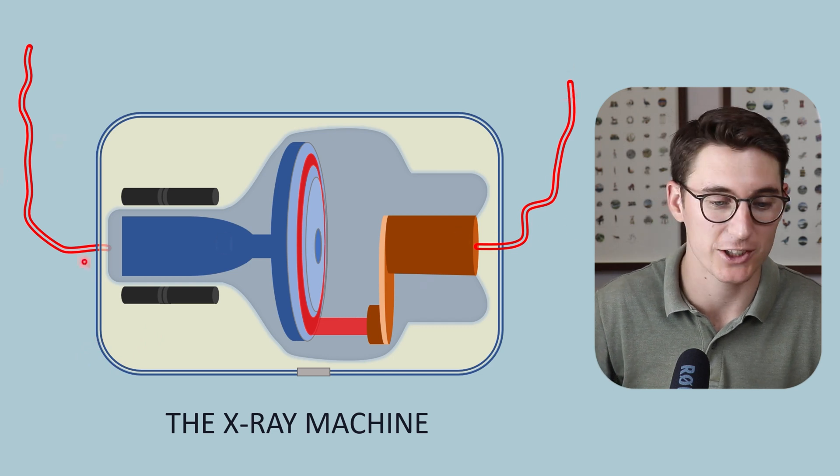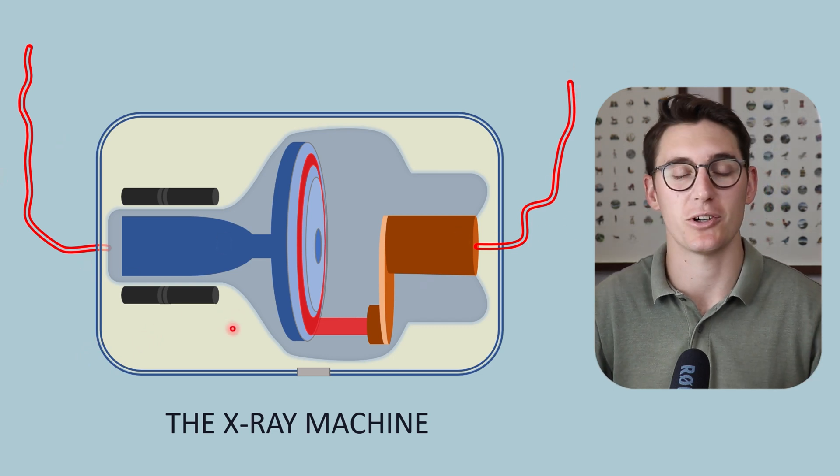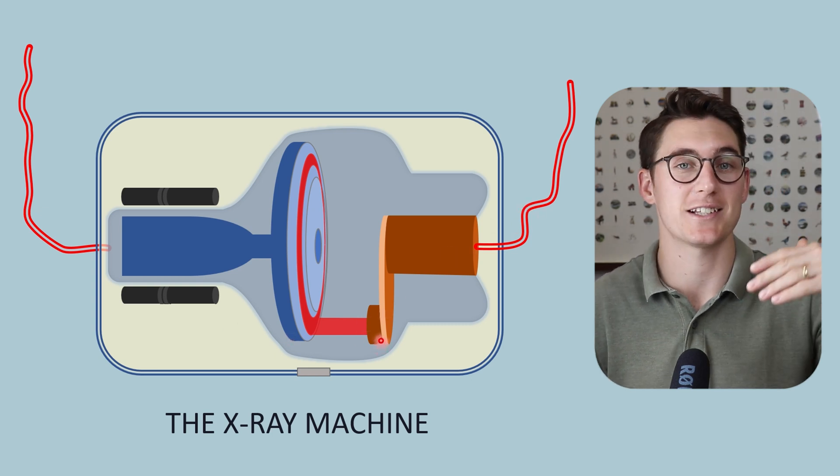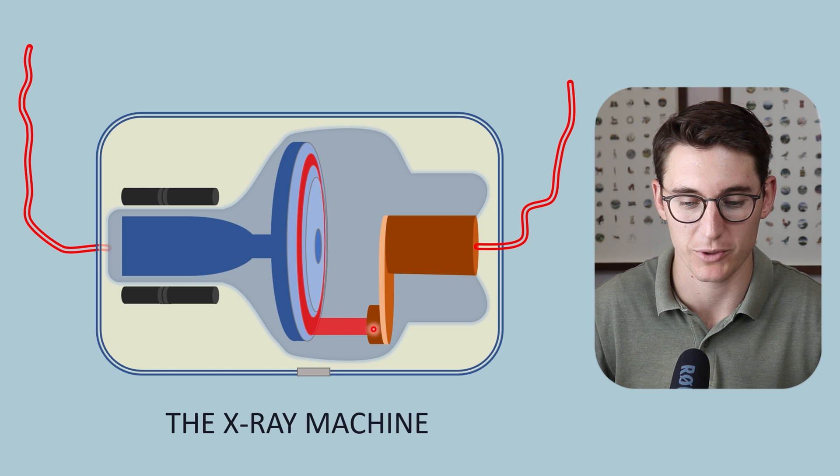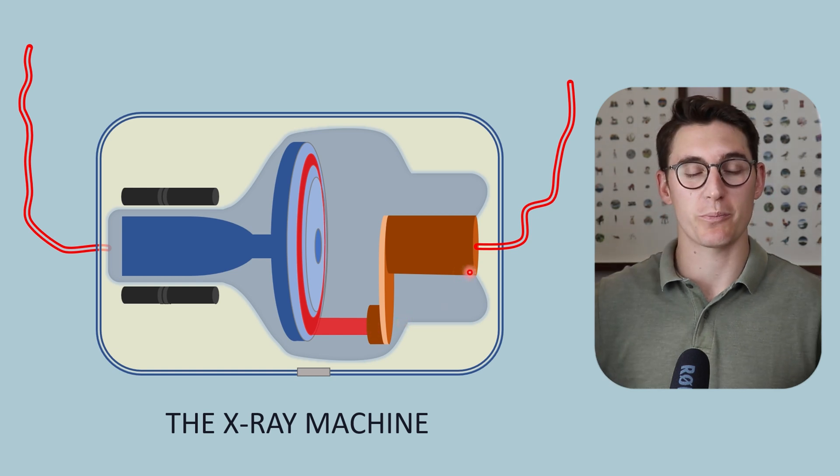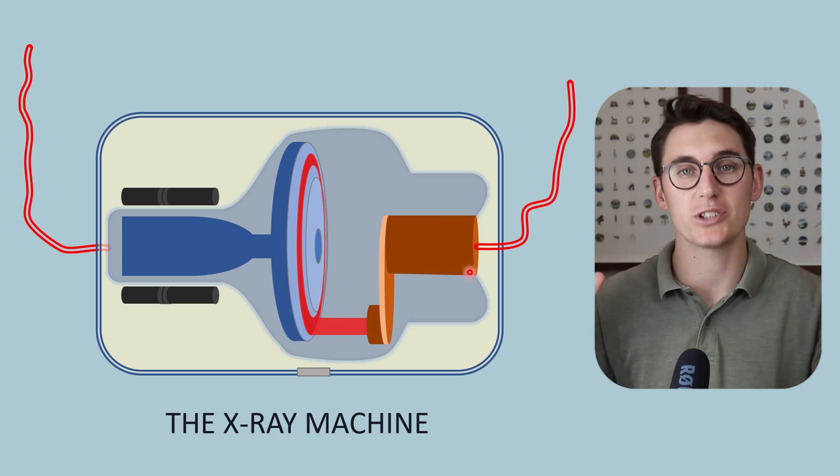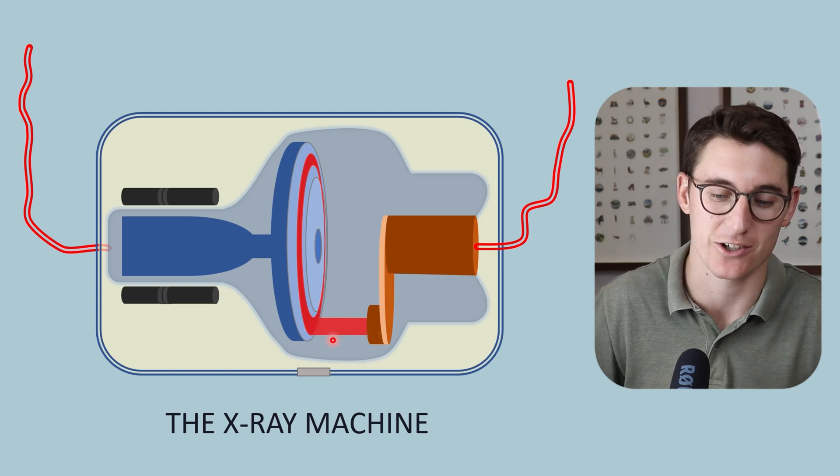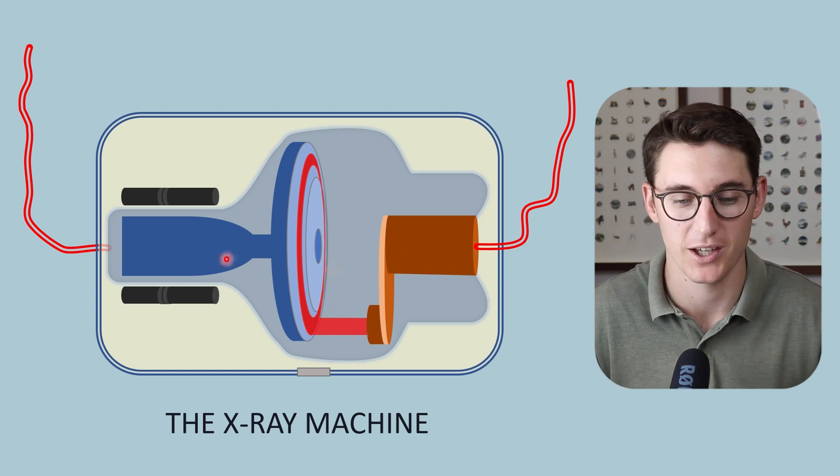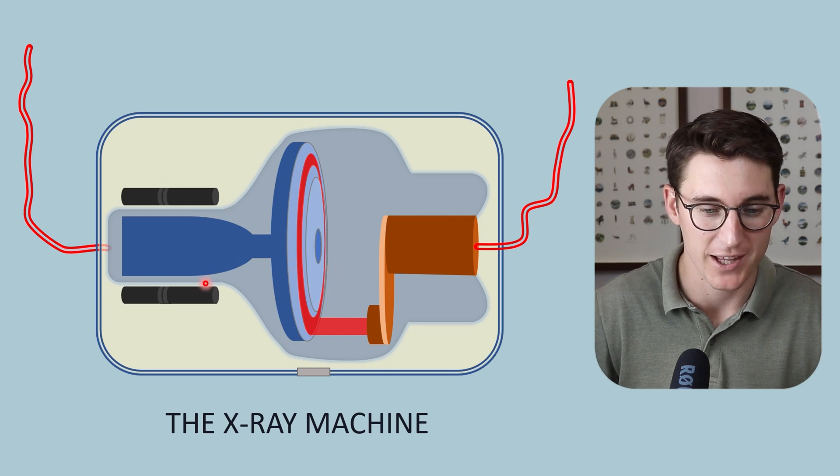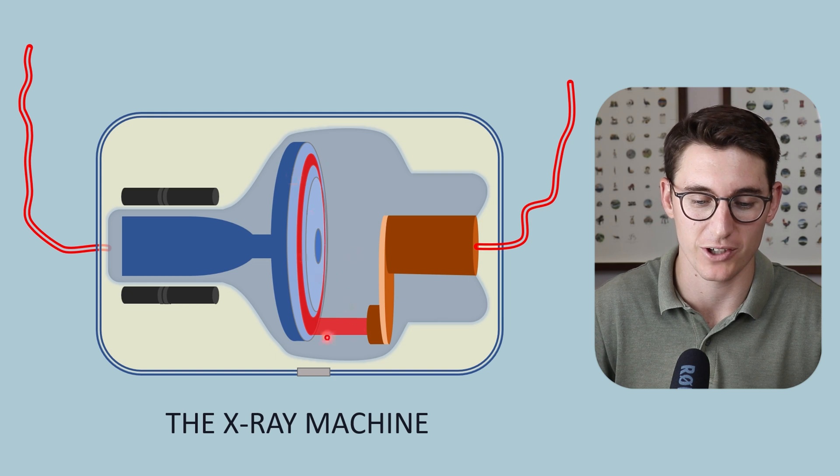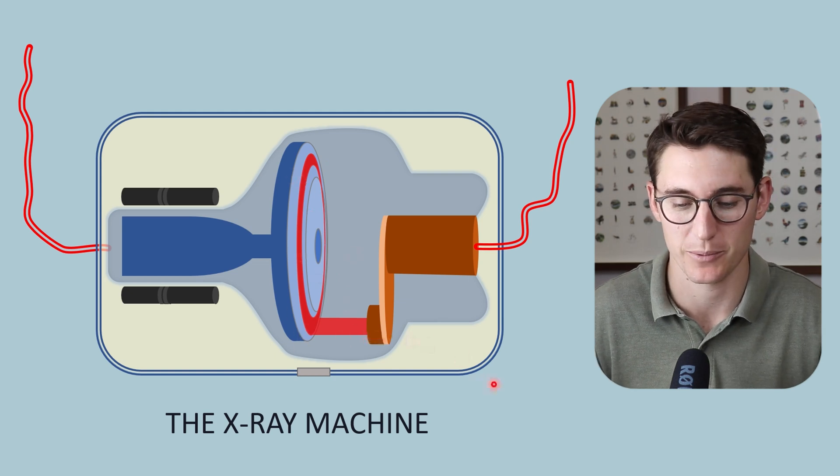We then have power supply to our x-ray machine that has multiple functions. First, we run current through our filament and create electrons through the process of thermionic emission. Secondly, we want to provide a tube potential, a voltage difference between our cathode and our anode that accelerates those electrons towards our anode. We also have a power supply that goes to these stator motors that controls the rotation of the anode, that allows the anode to deal with all that heat buildup.